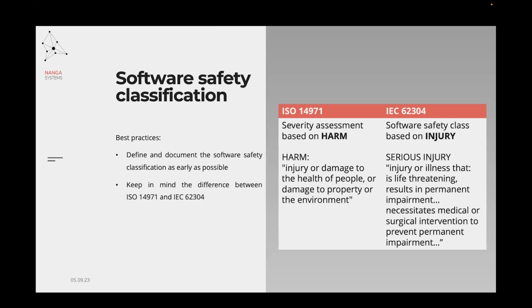So basically, the major difference here is that in case of IEC 62304, we do not take damage to property or to the environment into account, which is quite important, because if we follow the standard risk management approach according to ISO 14971, our classification might result in a higher classification class, and that again leads us to higher or more requirements to comply with, and higher development costs.